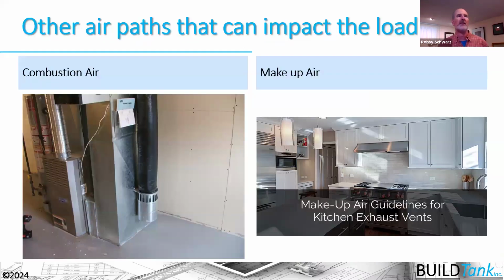Now, there are some other pathways for air to impact the loads of our houses that aren't taken into account as directly. Combustion air comes into our homes, and the combustion air in the picture on the left here is put into a container to try and ensure that when the furnace isn't running and utilizing that combustion air, that combustion air isn't going to just migrate and flow around the house. Makeup air guidelines for kitchen vents are also an issue there. We should be conditioning that air separately from our HVAC systems. But if we're not, we really should be taking into account the amount of makeup air that we're bringing in for that kitchen hood, and understanding that that's creating an additional load for the house as well.